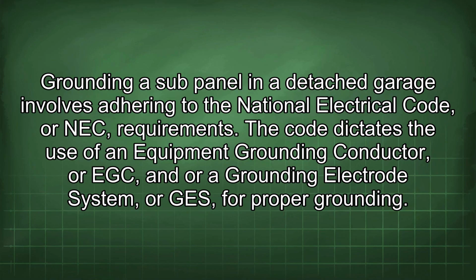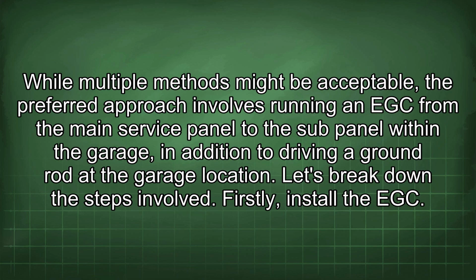Grounding a sub-panel in a detached garage involves adhering to the National Electrical Code, or NEC, requirements. The code dictates the use of an equipment grounding conductor, or EGC, or a grounding electrode system, or GES, for proper grounding. While multiple methods might be acceptable, the preferred approach involves running an EGC from the main service panel to the sub-panel within the garage, in addition to driving a ground rod at the garage location.